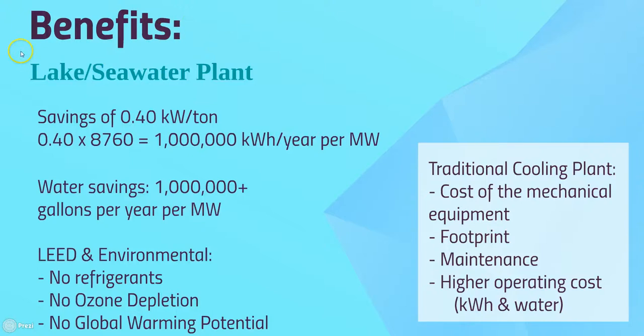All right, now let's talk about the benefits of the river, lake, or seawater plant. And this is essentially an overview of a lot of the items that we'd already talked about. Let's start out with the savings. It's 0.4 kilowatts per ton as shown previously. And that 0.4 kilowatts per ton we take and multiply out at 1 hour, taken through the entire year. There's 8,760 hours in a year.